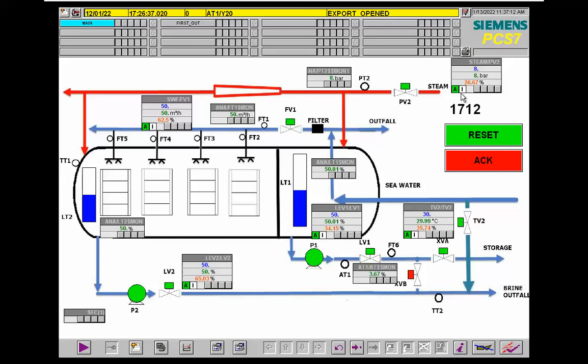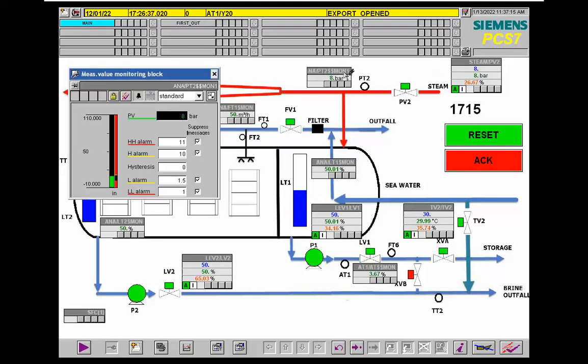I want to increase the steam. The high-high alarm — the trip level for steam — is around 11 bar. I want to increase that, and you can see that after passing this limit, if we violate this limit, the plant will be shut down.